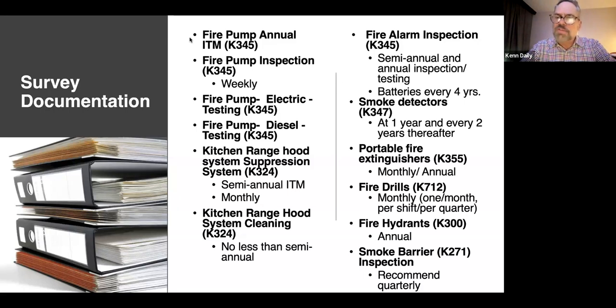Fire hydrants, some of you may have to do your own fire hydrants, which the fire hydrant testing is a clear flow test, and then the smoke fire barrier inspection. So again, this is one I recommend doing, because it's a leading citation in Pennsylvania, 271 or 374. There were a lot of penetrations or holes left in your barriers. And so making sure that these are corrected and corrected appropriately with the correct caulking material, using the correct product and done correctly.